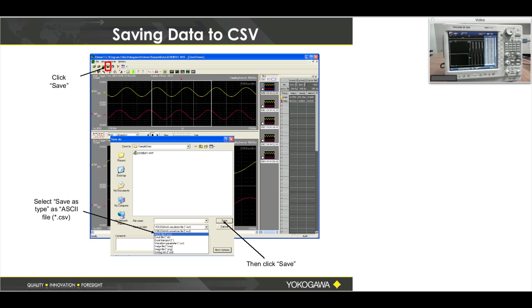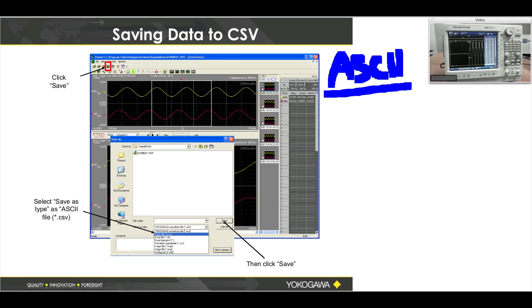Regarding ASCII files — on the DL850 it's called an ASCII file, also known as a CSV file. I would discourage doing the ASCII conversion on the instrument itself. If you need to do ASCII, do it with X-Viewer because it's free, it's easy, and it's faster. Your files are going to be very large, so it's important to do that on your PC.